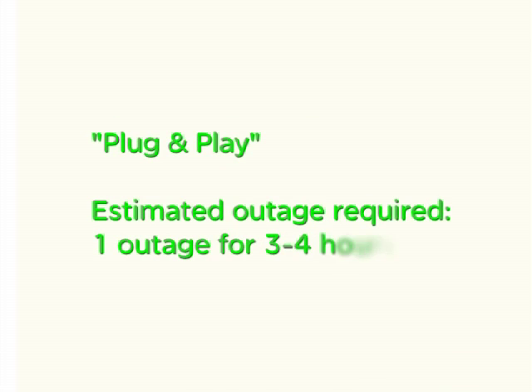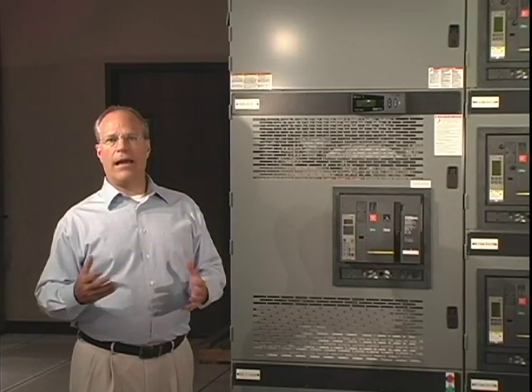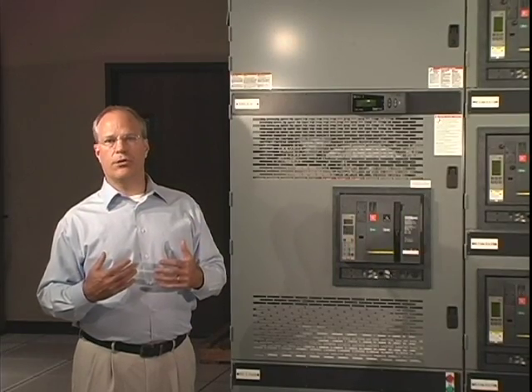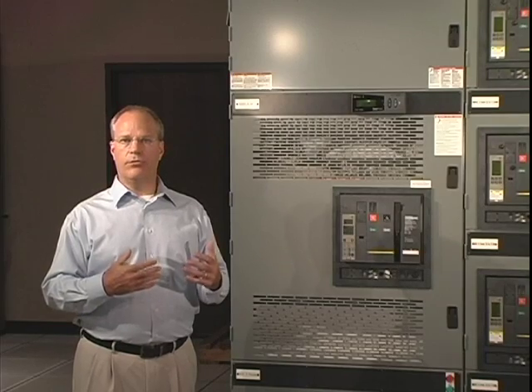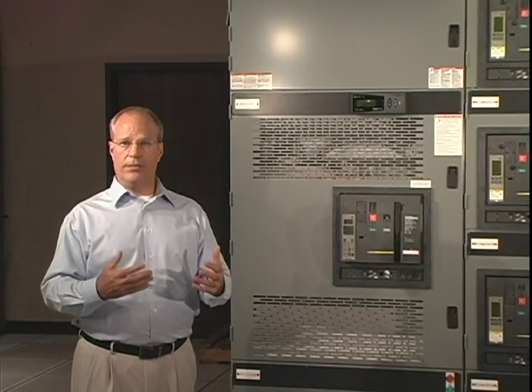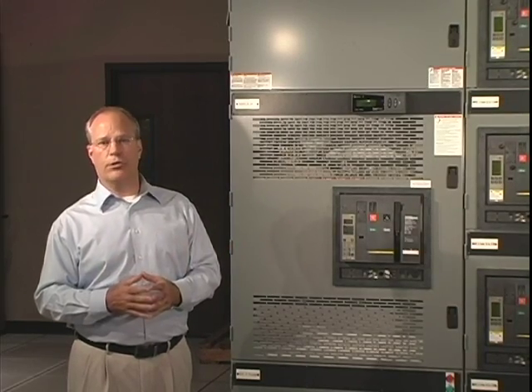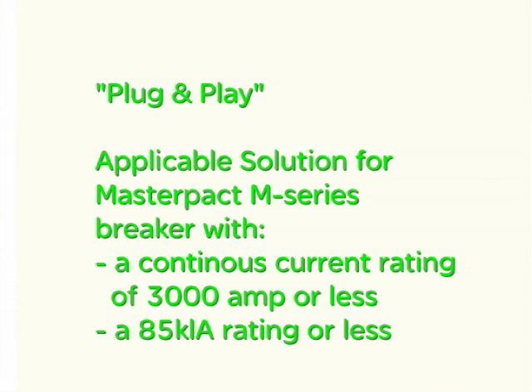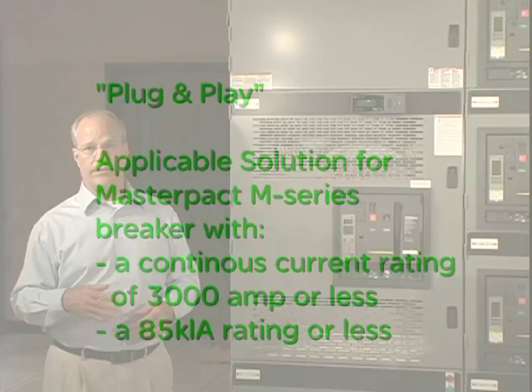The first option is the plug-and-play approach. An outage must be coordinated, the duration of which could be a total of 3 to 4 hours, where the actual removal of the existing M-Series circuit breaker occurs and the modification to the existing cradle takes place to accept the new Masterpact NW circuit breaker. This option only applies to the M-Series breakers that have a continuous current rating of 3,000 amps or less, and the existing circuit breaker has an interrupt rating of 85,000 amps interrupting or less.